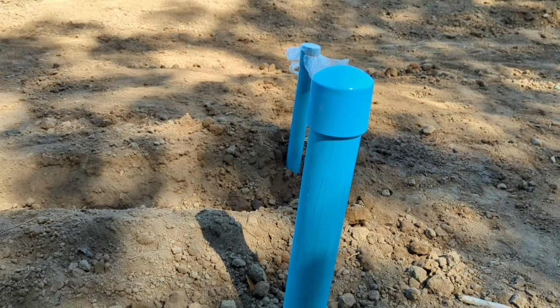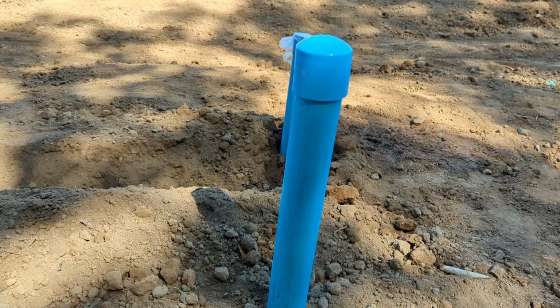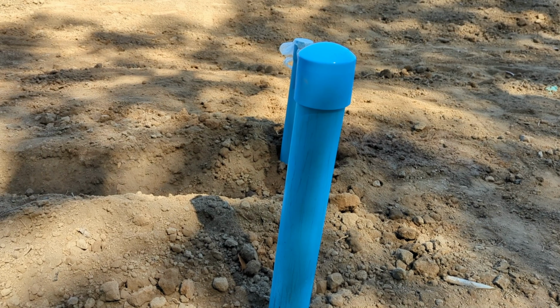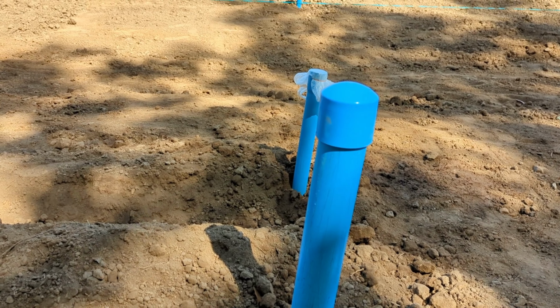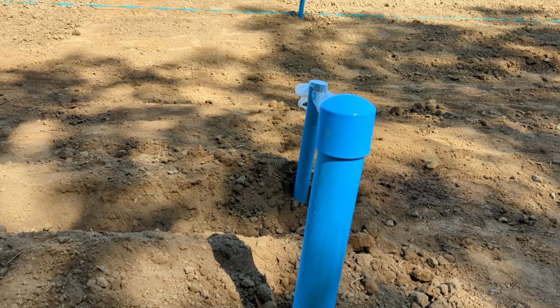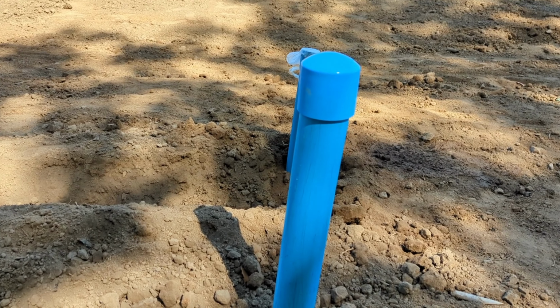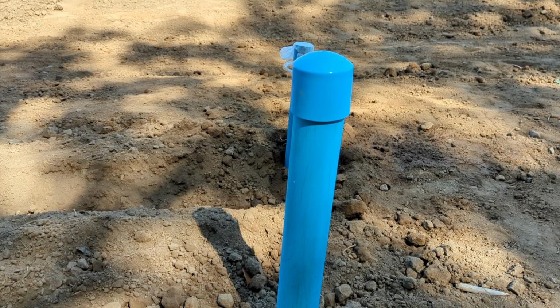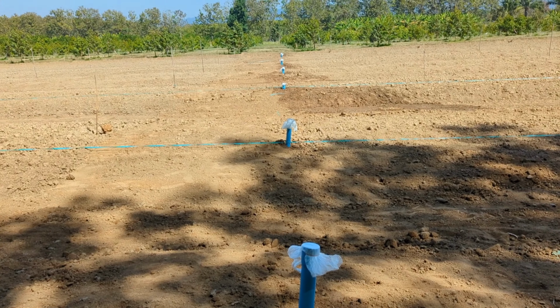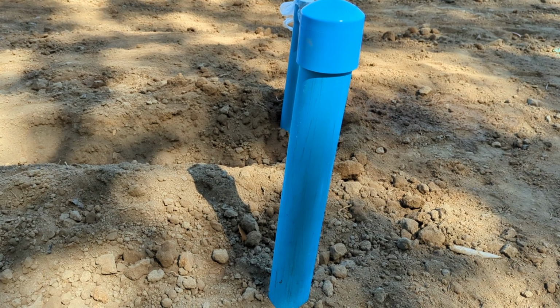I have it sticking out of the ground here for 2 reasons. First, I'm able to flush my lines — if you get debris in there from installing your system, you take the cap off, turn your system on, and let it flush. I already did that with the test we ran.